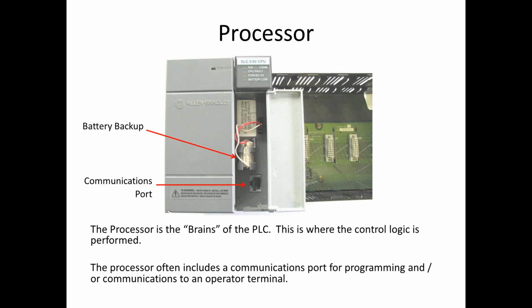So the processor is the chip, or the brains, of the PLC. This is where the control logic is actually performed. You can see by this drawing there's a battery backup. Should the power supply fail or lose power, the battery backup will keep the chip running so you don't lose the programming that's in the chip. It also many times will include a communications port for programming, or where the SCADA system, the operator interface system, will plug in, and you can bring a laptop down and plug into the PLC right there, so you can troubleshoot right at the PLC in many cases.